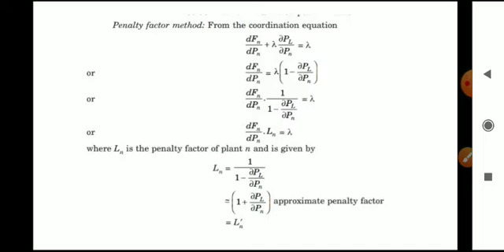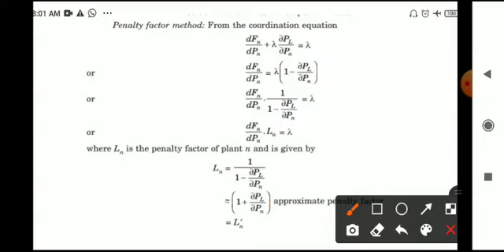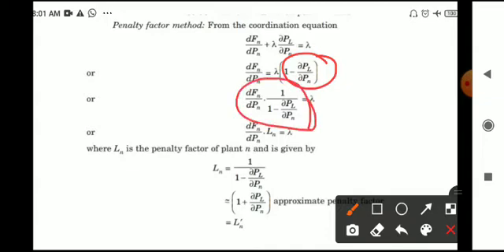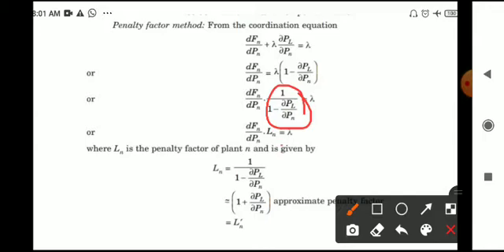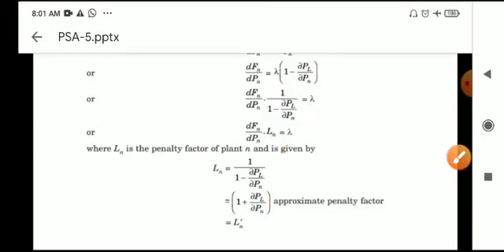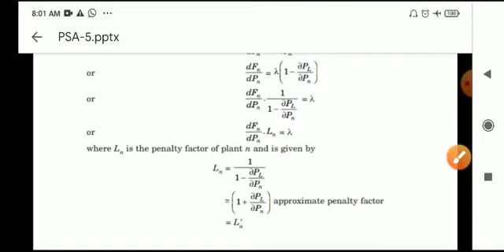From the coordination equation, dFn/dPn is equal to lambda into (1 minus ∂PL/∂Pn). By rearranging, dFn/dPn into 1/(1 minus ∂PL/∂Pn) is equal to lambda. That term 1/(1 minus ∂PL/∂Pn) is replaced by Ln, so the equation becomes dFn/dPn into Ln is equal to lambda, where Ln is our penalty factor.